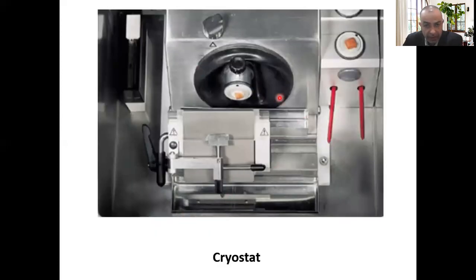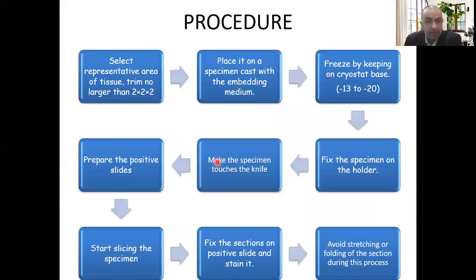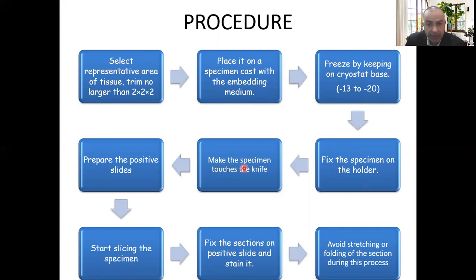This is the cryostat viewed from above — a photo taken during work. The procedure: select the representative area of the tissue. Trim to no larger than 2×2×2 mm. Place it on the specimen cast with the embedding medium FSC 22. Freeze by keeping on the cryostat at minus 13 to minus 20. Fix the specimen on the holder, and make the specimen touch the knife. Prepare positive slides — this prevents slipping and rolling. Start slicing the specimen and fix the sections on the positive slide.